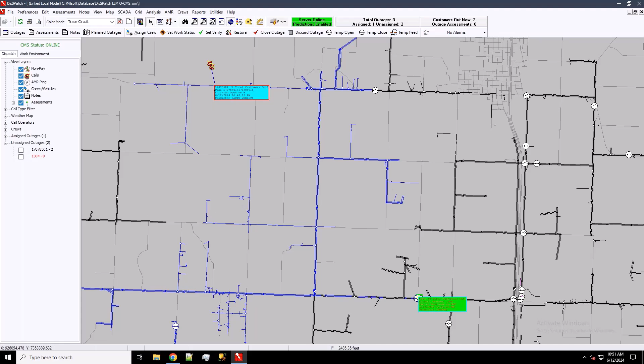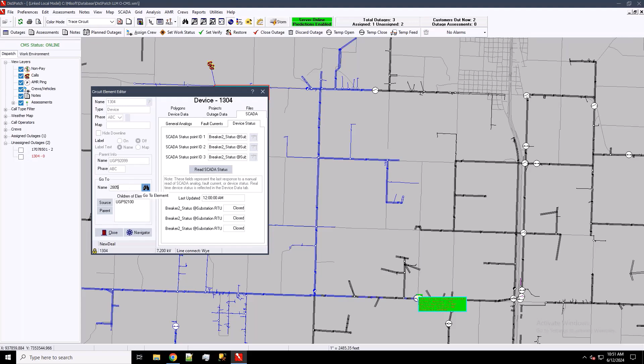One other scenario we want to demonstrate, which we are seeing more and more commonly, is getting SCADA devices downline that are being controlled. When we first started working with SCADA integrations, it was very common to have every feeder breaker controlled by SCADA, but more and more regularly we're seeing automated restoration schemes where we can have SCADA controlled devices further down the circuit. That's really changing how SCADA integrations work with our system, and reflects a broader acceptance of SCADA in general, taking advantage of the technology. And so we wanted to try to demonstrate that as best we could.